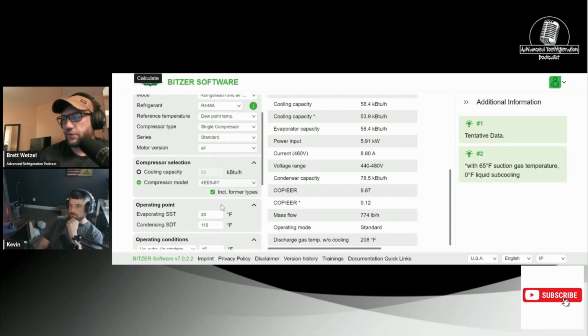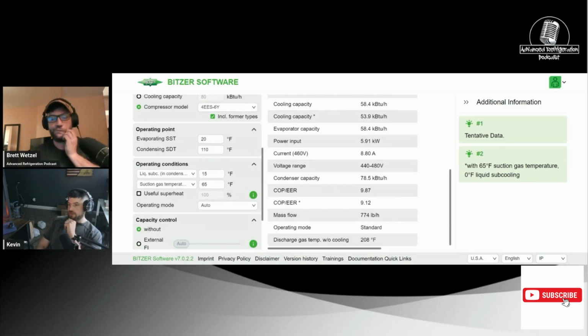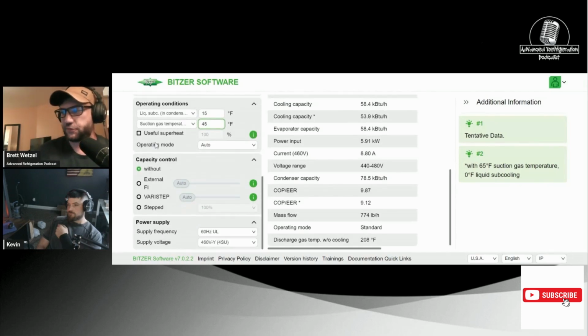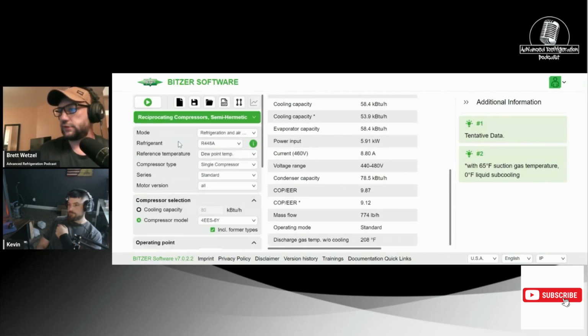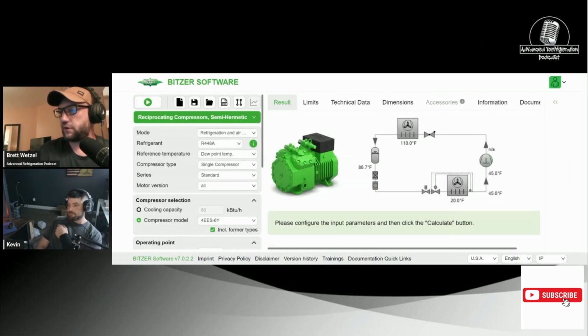So what do you want to mess around with now? You want to change the suction temperature from 65 to 45 and watch what happens to the discharge temp. Suction gas return temp? Yep. 65 to 45. So that basically gives us about 25 degrees of superheat, right? Yep. All right, see what happens. Let me just take a quick screenshot so we can compare.